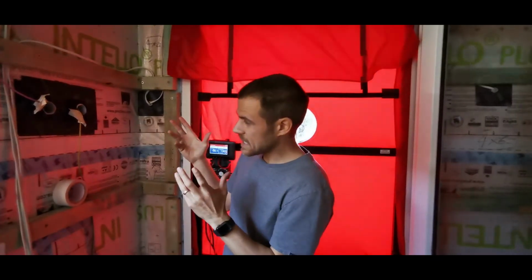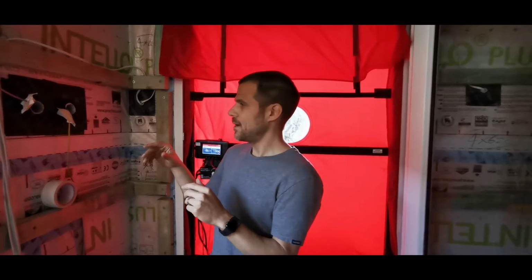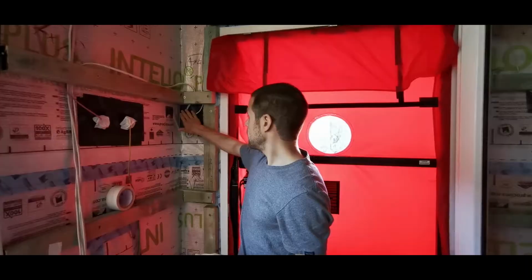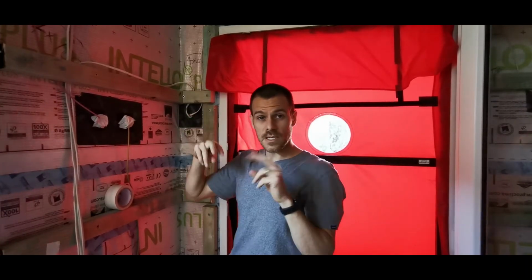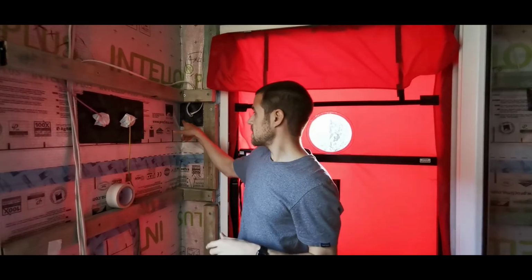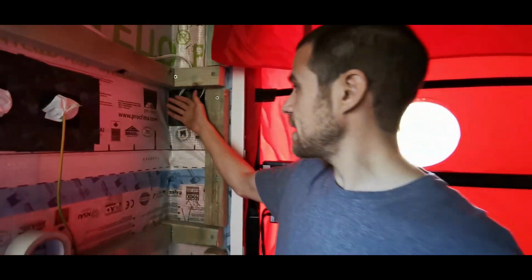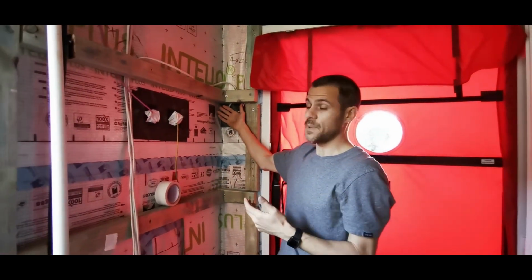And then you start to get a sense for what that means in terms of how big a hole I'm looking for, or how many holes I'm looking for. Just because something doesn't look sealed on the inside doesn't mean it's actually going to be a leak. This might be sealed on the far side, so it might not be a problem.